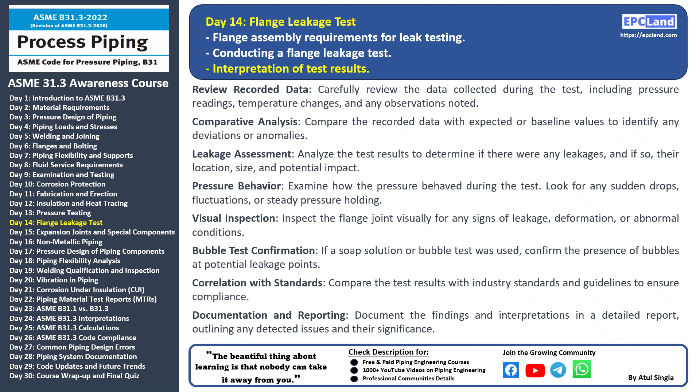Review recorded data: carefully review all data recorded during the test, including pressure readings, temperature changes, and any other relevant observations. Comparative analysis: compare the collected data with expected values or baseline measurements and identify any variations or anomalies that may indicate issues. Leakage assessment: analyze the results to determine if there were any leakages; if leaks are detected, assess their severity, location, and potential impact on the system. Pressure behavior: study patterns such as sudden pressure drops, fluctuations, or consistent pressure holding.